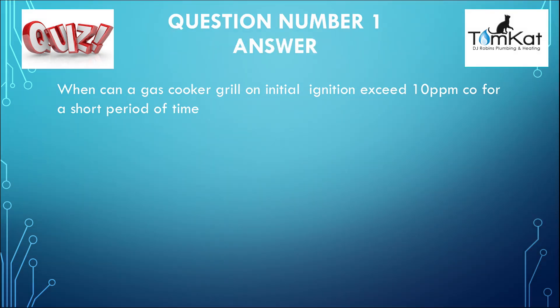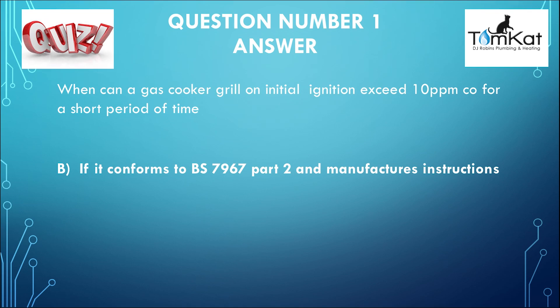Let's get on with it and find out if you got 10 out of 10. Looking at the answer for question number one: when can a gas cooker grill on initial ignition exceed 10 parts per million CO for a short period of time? The answer is B — if it conforms to BS 7967 Part 2 and manufacturer's instructions. That was the answer for question number one.